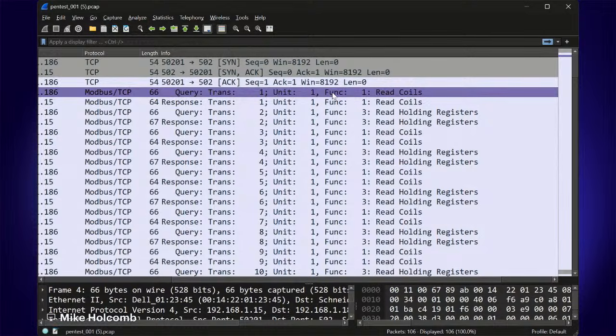It does that by sending out signals. But ultimately, it has to bring in data from sensors and store it in memory in what they call coils and registers. Coils are where we store information as zeros and ones. It's binary data, just zeros and ones. In the registers, that's where we can store larger values, anything between 0 and 65,535.